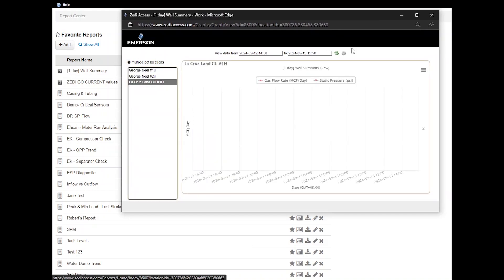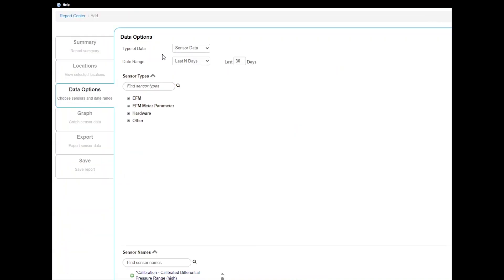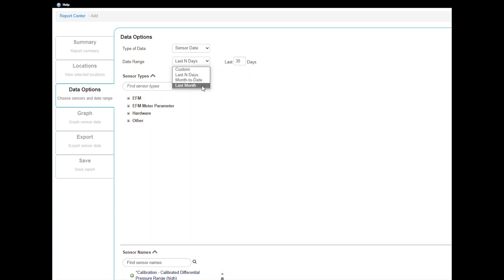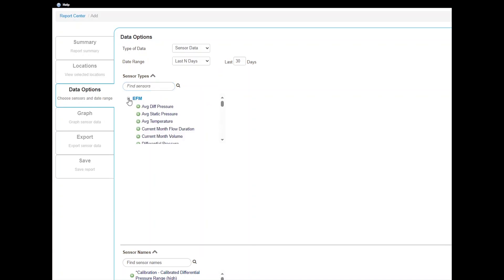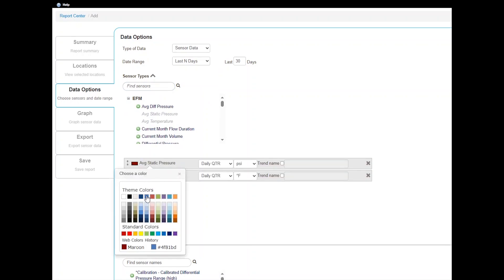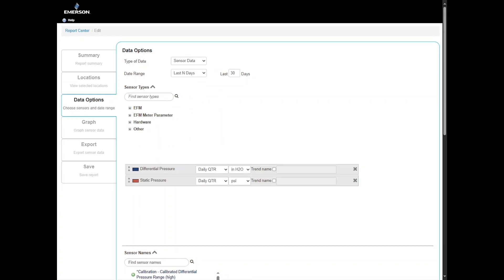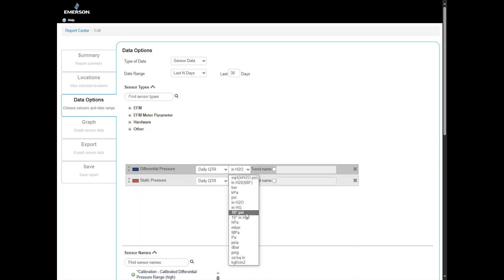To create a custom report, select Add. Custom reports can be saved either as user-specific or company-wide. Company-wide reports will be available to all users who can add them to their favorites. To customize a report, select Filters. Type of data will always be sensor data. Select the date range. Options include number of days, custom, specific start and end dates, month to date from the start of the month to today, and last month, data from the previous month. Choose Sensors. You can search or open folders to select the sensor. Use the green plus sign to add a sensor. You can adjust the color of the sensor data by selecting the color icon next to the sensor name. Adjust the data resolution to daily QTR, hourly QTR, or raw data. Raw data shows every data point collected, while the QTR provides averages or totals for a 24-hour period. Adjust the units of measure, if applicable, which will only affect this report and not the site display. Customize Trend Name will change the name of the sensor for the graph or report, if needed.